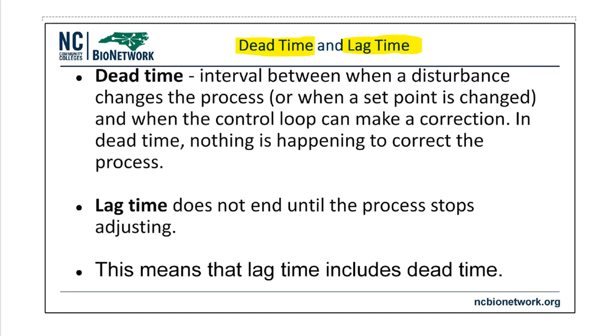It was just a window that was kind of acceptable in a roundabout way. But these two terms are slightly different, because one is called not a dead band, but dead time, and the other is called lag time. These are two things that we want to look out for on the manufacturing side as well. If I read the definition of dead time here, it says the interval between when a disturbance changes the process and when that control loop can make a correction.